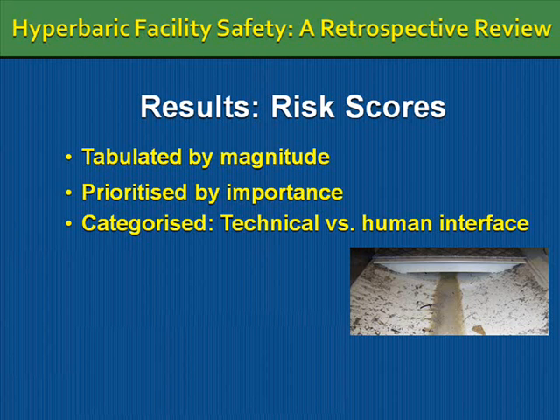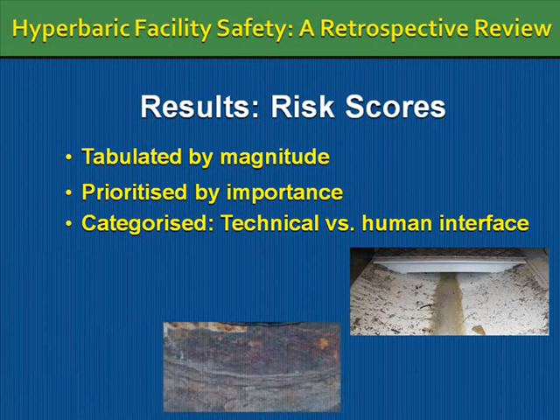That's only because your chamber doesn't have floorboards. You can think of the human waste and everything that's lying down there, and they tell me very proudly that once a year they lift up the floorboards and clean out the bilges. That's really not very well done. That's what it looks like if you pay no attention to it. So after several years, that will lead to that, very serious rust and corrosion.